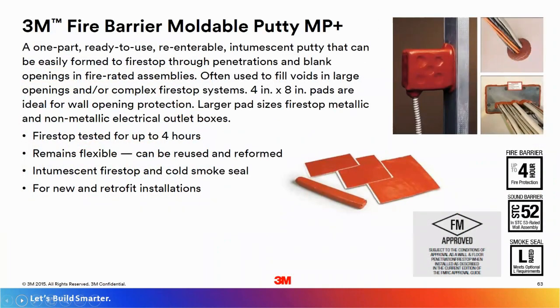This is probably one of the most popular products amongst the electrical trades. This is our moldable putty, or our MP Plus. It's available in a putty bar, and we also have the putty pads. The putty pads are typically used on the outlet boxes. We have tested systems for up to 4 hours using putty. The putty will remain flexible and can be reused and reformed. Of course, it's an intumescent fire stop material, so this will expand when it sees the heat of a fire and act as a cold smoke seal as well. This can be used for new and retrofit installation.